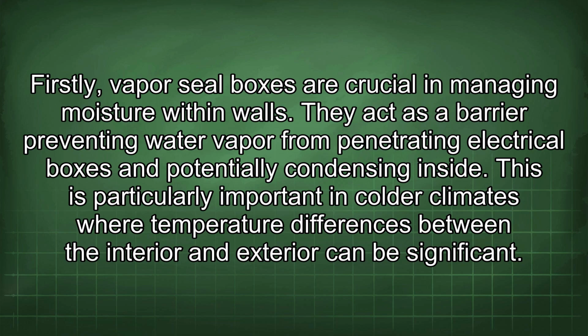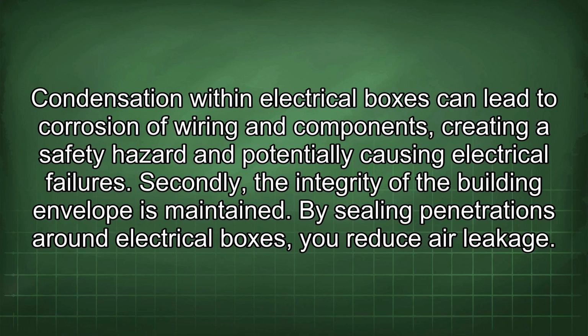Firstly, vapor seal boxes are crucial in managing moisture within walls. They act as a barrier preventing water vapor from penetrating electrical boxes and potentially condensing inside. This is particularly important in colder climates where temperature differences between the interior and exterior can be significant. Condensation within electrical boxes can lead to corrosion of wiring and components, creating a safety hazard and potentially causing electrical failures. Secondly, the integrity of the building envelope is maintained.